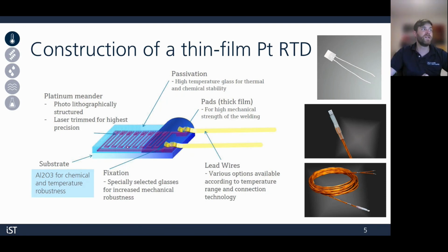So aluminum oxide, platinum. This is the 3850 platinum that's pretty standard in Europe and mostly around the world. This passivation glass, which we develop in-house, we have different glasses available for different temperature ranges. So in this case, the glass is the same as what you would see on our 7W series. So if you go to our website and look at the downloads and then 700-degree sensors, it's basically the same thing. If you look at the 232 chip, the core difference is that, as I mentioned, slightly different mask that we're using, so a slightly different shape of the resistor, and we're adding in all these screening tests.